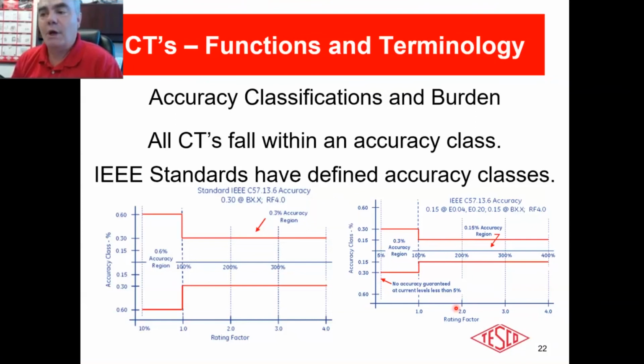The reason for that was they were installed on, obviously, very large services, which only expected to get to the very upper level of that once in a blue moon and for very short durations. The manufacturer managed to get all those windings into a package, but said, you can't put 6,000 amps on that and let it run for 2 days because it will break down. But if you're only going to put 6,000 amps on for half an hour or 15 minutes or less than an hour, it'll actually work just fine, but don't keep it on for an extended period. So for the very largest transformers, you may actually see a thermal rating factor of less than 1.